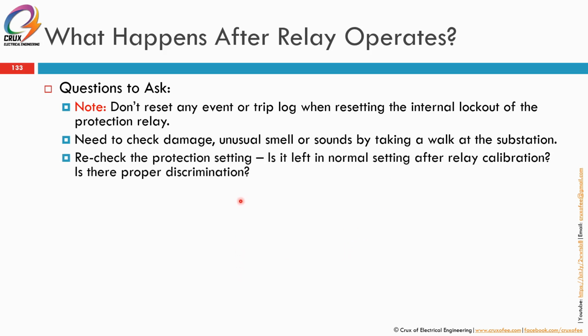So you might also need to reconfirm the protection setting. Is it left in the normal setting after relay calibration, and is there proper discrimination? This first issue normally happens after relay calibration. People forget. They do relay calibration and forget to reinstate the normal setting. And the tripping might happen maybe within 6 months, 1 year or 2 years. And when you find out, actually it's not due to an actual fault. It's actually due to wrong discrimination, because the setting has been set at a lower setting than the actual required setting.